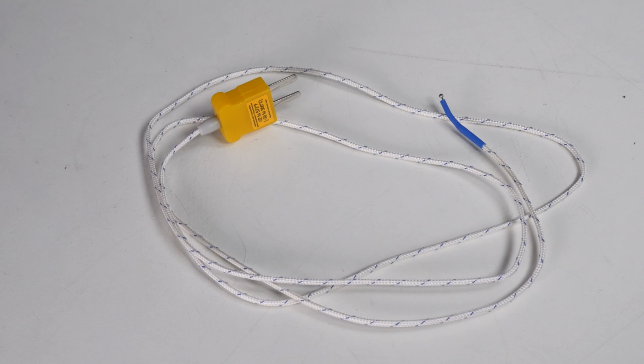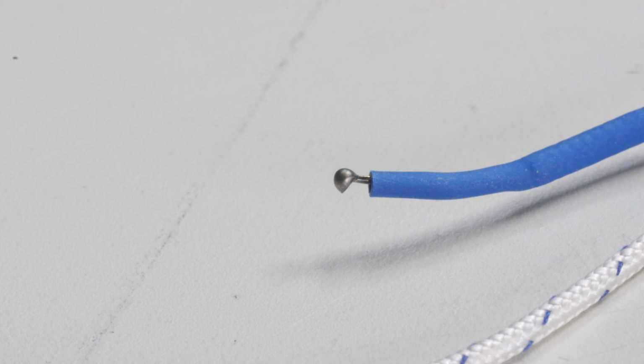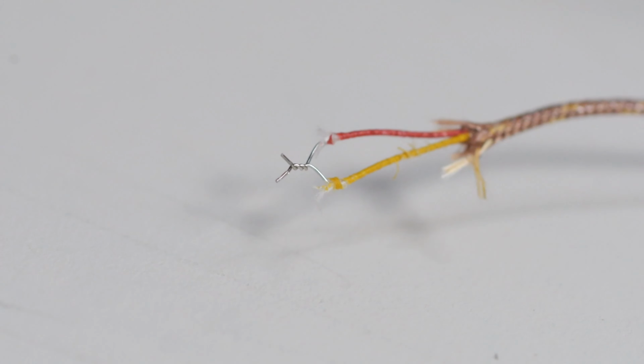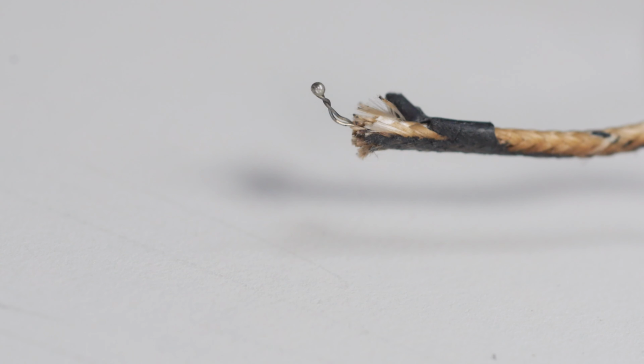Since a contact is sufficient between the wires, the question is whether the wires need to be spot welded. Why not just twist the end of the wires? A junction weld break is not a major problem if you have a good clean contact with the wires at the hot junction area and a strong enough pressure to hold the conductors together. If you do not, then you will get a reading, but it could be in error, and significantly in error, depending on the contact. Also, if the temperature is high, the wires will become oxidized. The chances are you will get bad contact and an incorrect reading by an unknown factor.